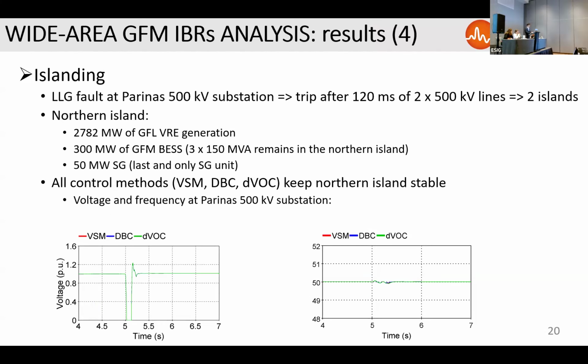All right, second test is, well, the third test is the islanding. Now, there is a fault which is disconnected. Well, actually, the fault clearance is basically disconnecting two lines of the 500 kV corridor. And in this case, you basically have two independent islands, one in the north, which is smaller, and one in the south, which is larger and has a lot of synchronous generators connected, so there are no problems with it. However, in the north, you only have about 3,000 megawatt generation and only one synchronous generator unit.